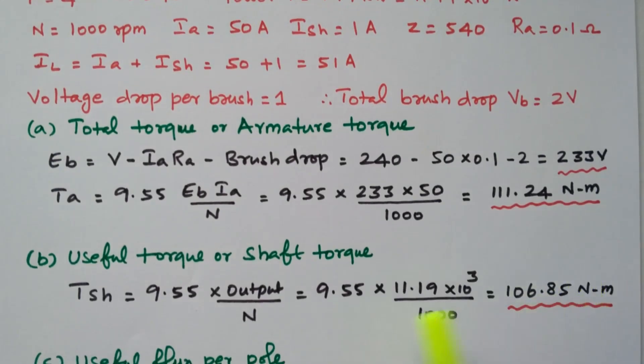Now we find the useful torque, or shaft torque. The torque developed in the armature has some losses; the remaining is available as shaft torque. The formula is T_shaft = 9.55 × output / N = 9.55 × 11.19 × 10³ / 1000 = 106.85 N·m. The shaft torque is less than the armature torque because of friction and windage losses.